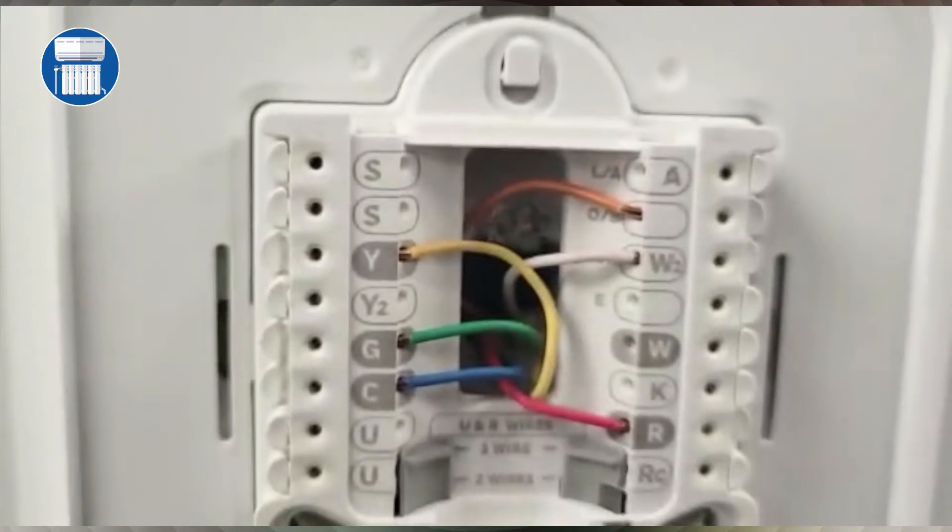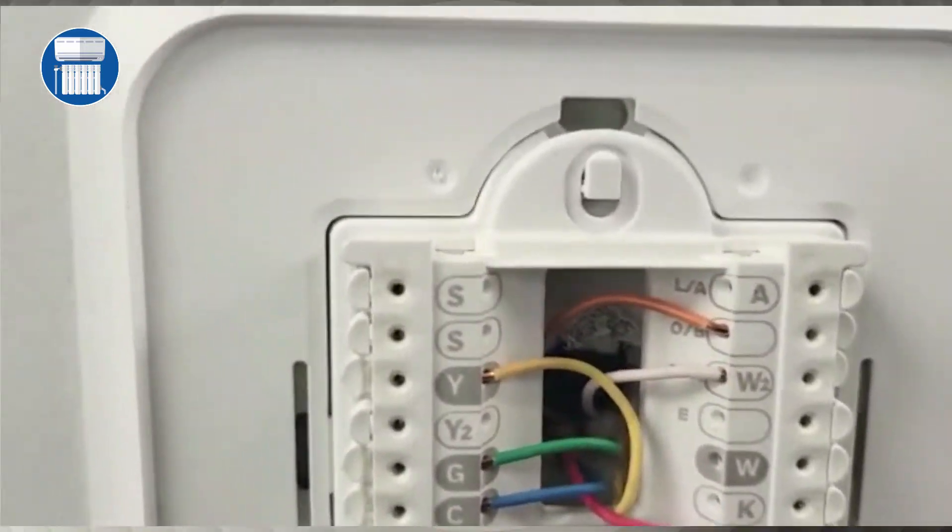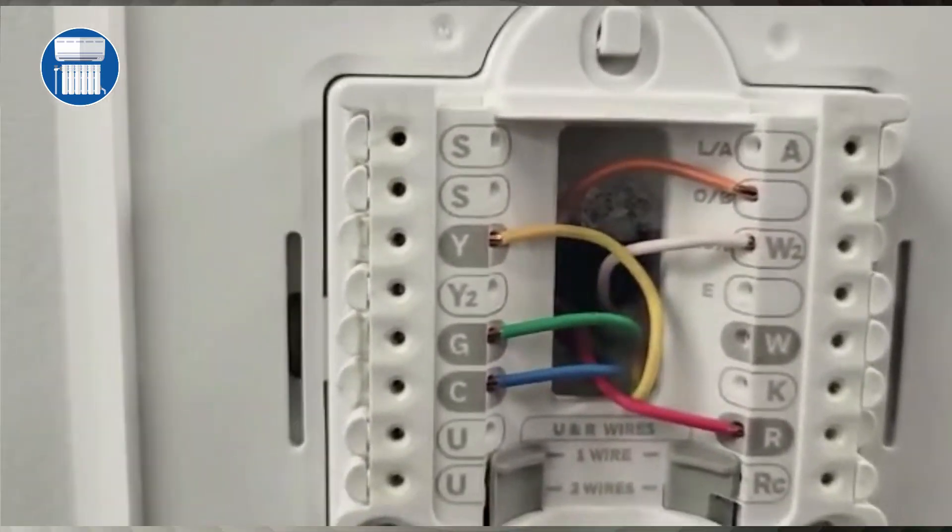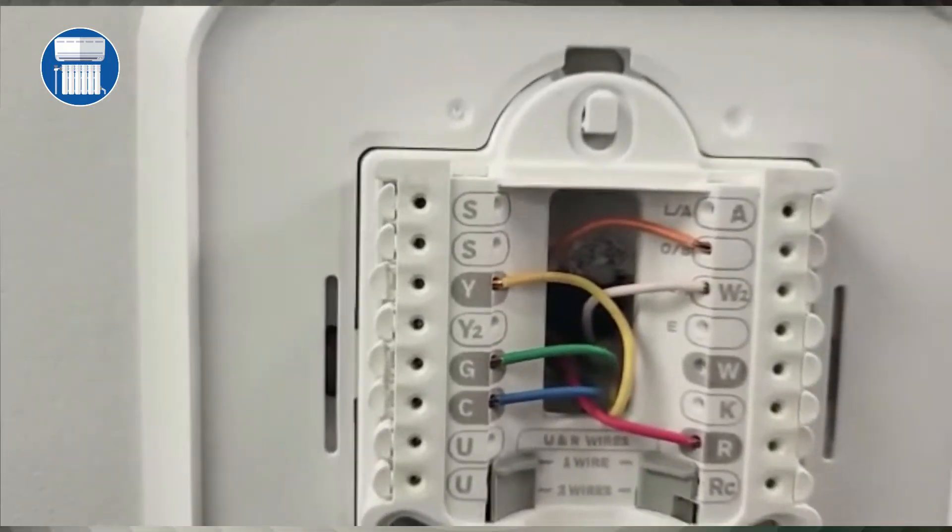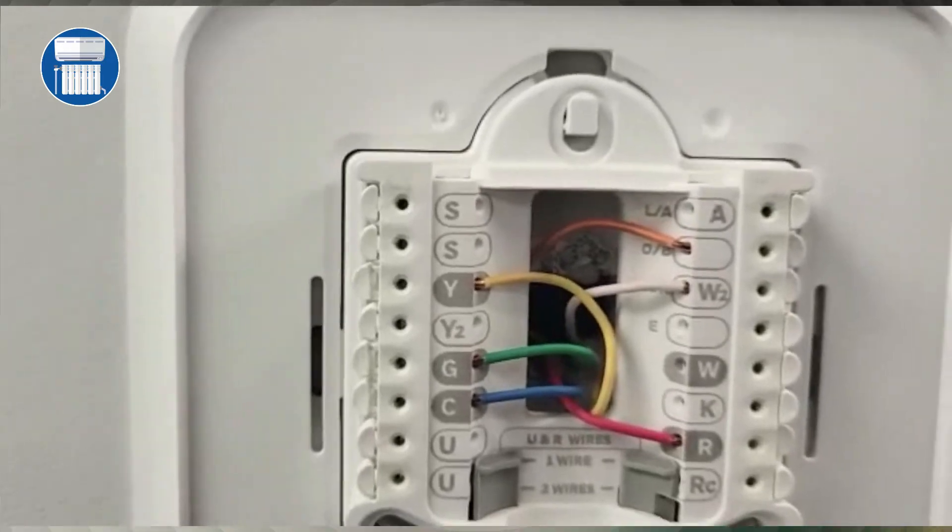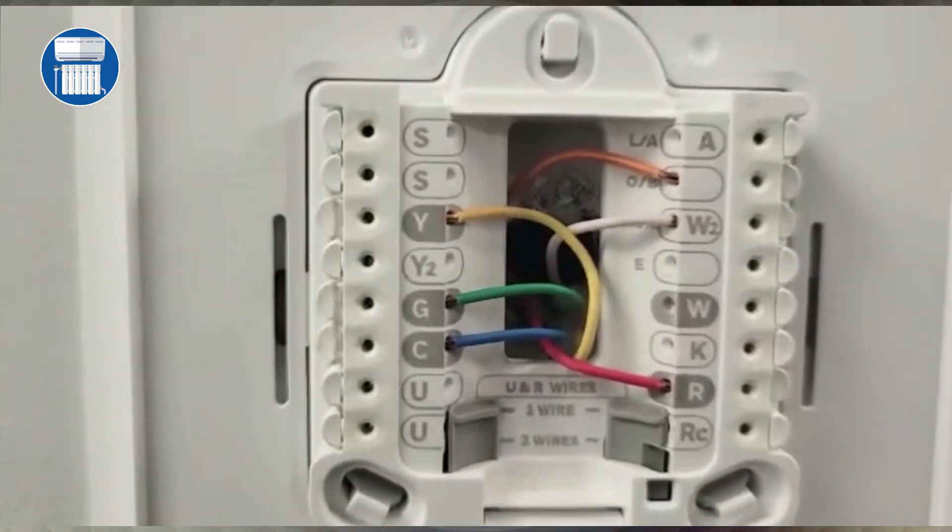That's exactly how you wire up the thermostat. The only difference you're doing here is you're putting on that orange wire to your OB terminal. That's the only thing you're doing different here compared to doing it for a regular thermostat.